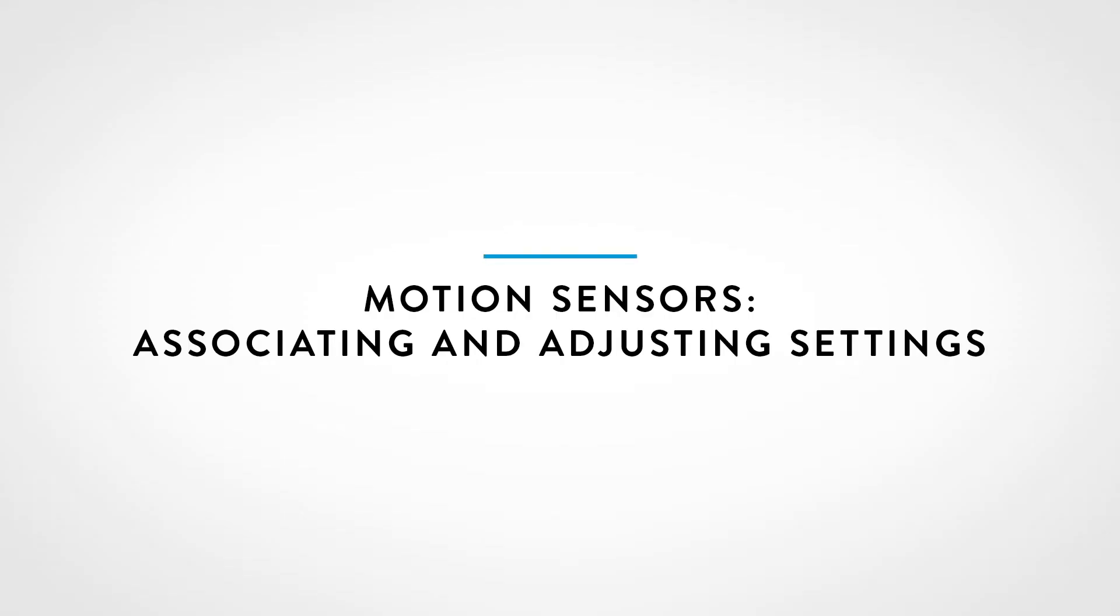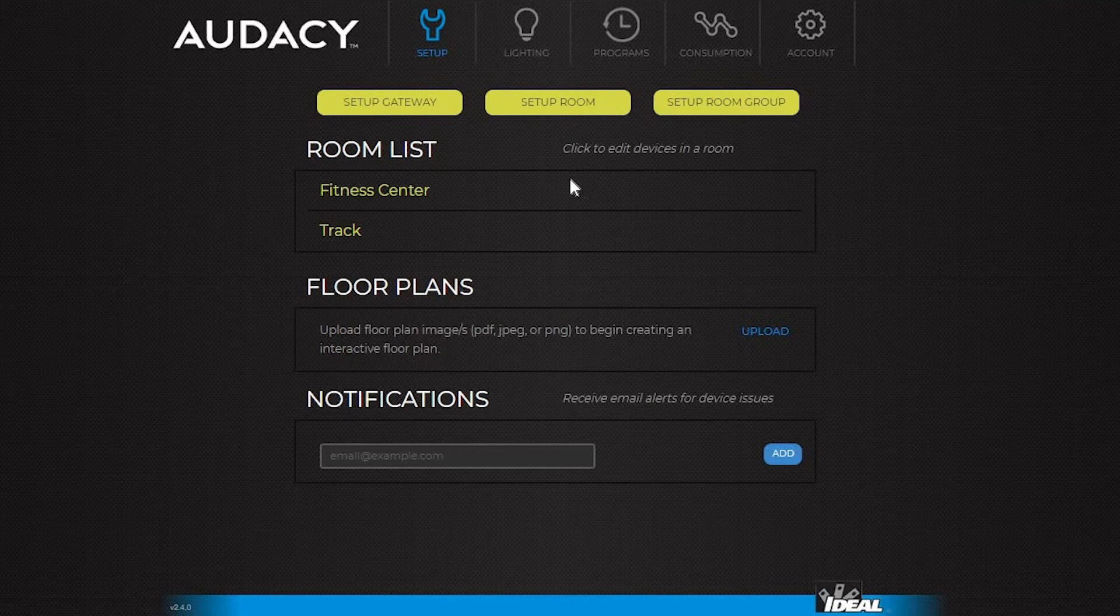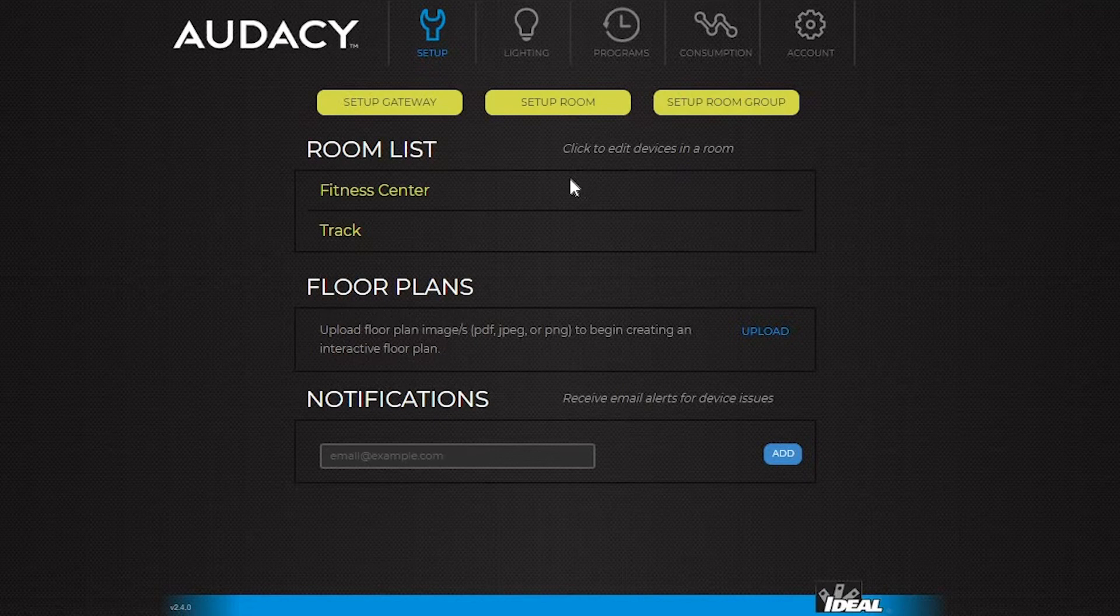Once a motion sensor is added, determine if the motion sensor should function in a vacancy or in occupancy mode. In vacancy mode, the lights must be turned on manually, while occupancy mode means the lights will turn on automatically when the room becomes occupied. Any motion sensors put in the room default to vacancy mode.